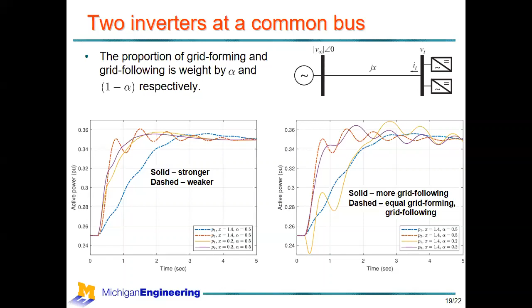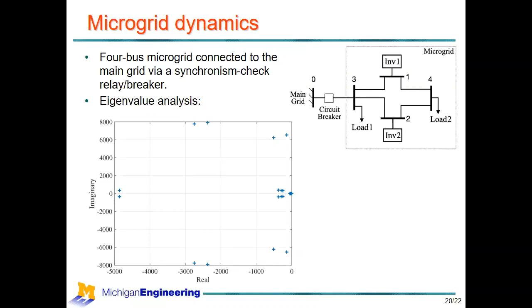The first thing was to look at the eigenvalues of that network. Sure enough, we find some very fast eigenvalues associated with the line dynamics and with the filter dynamics of the 2 inverters. Then the eigenvalues of interest from a control perspective are down here. So you get quite a wide range: line dynamics very fast, then some filter dynamics, and then the control sitting in between. In this particular case, at least, we didn't see a whole lot of interaction between the lines, filters, and controls, but certainly in practice people have seen some of those interactions.